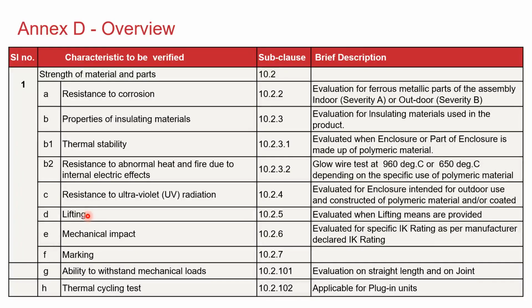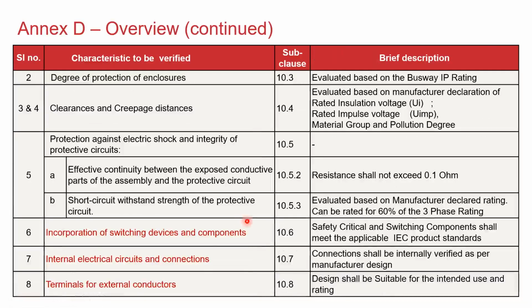Mechanical impact would be applied when an IK rating is declared. Marking test would be applied depending on what type of marking mechanism the manufacturer has used. Then there is a test called ability to withstand mechanical loads, which is done for a straight length and on joint. The thermal cycling test is applicable only when you have a busway with a plug-in unit. Otherwise, this may not be applicable.